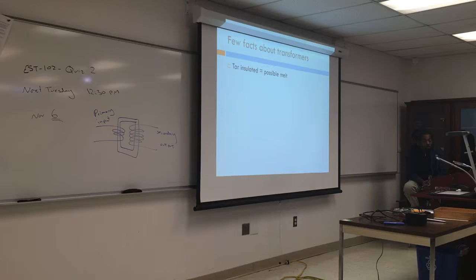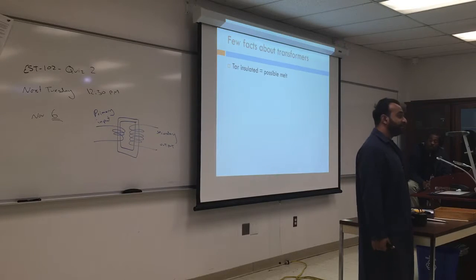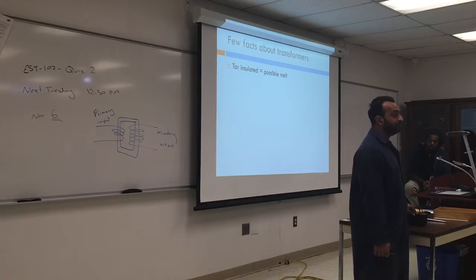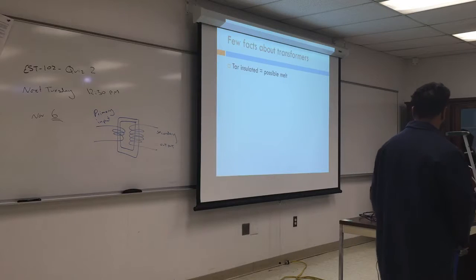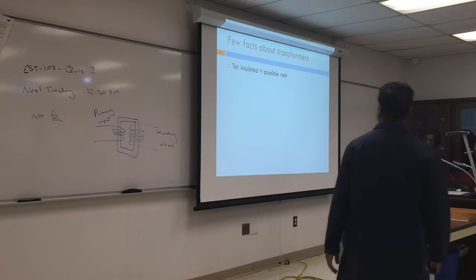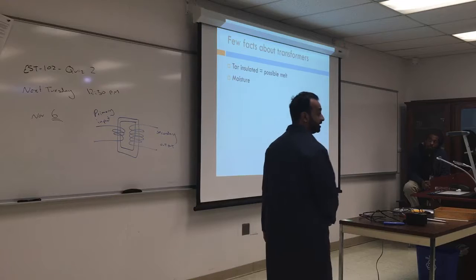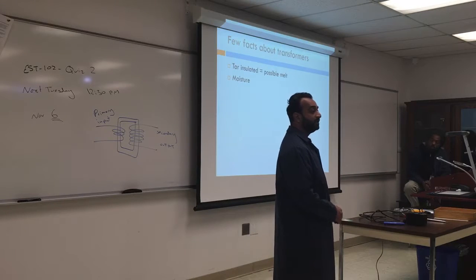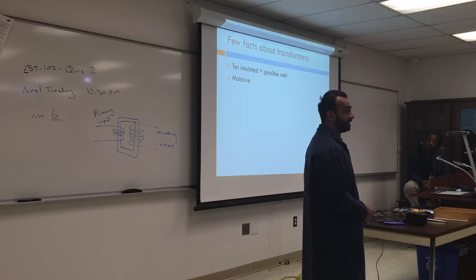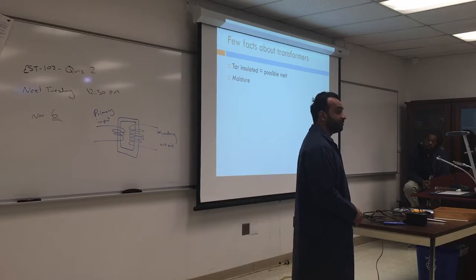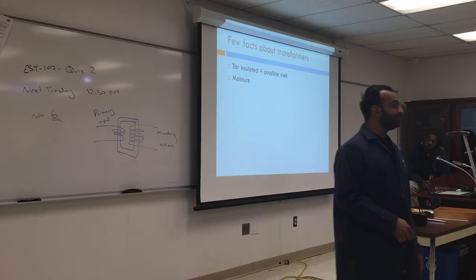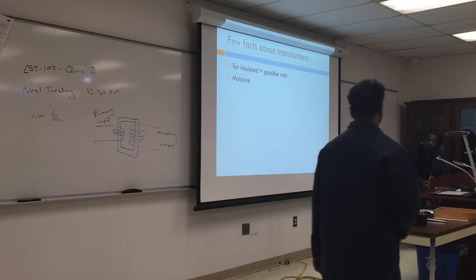So tar, that's why this thing is completely sealed. If you have moisture inside, it's probably going to grow some bacteria, and eventually it will feed on your tar and cause a problem. Moisture is an issue. This is supposed to be operated inside and outside. People place the transformer outside, but it's also supposed to be in a basement that is sealed, not open to the atmosphere or the elements.